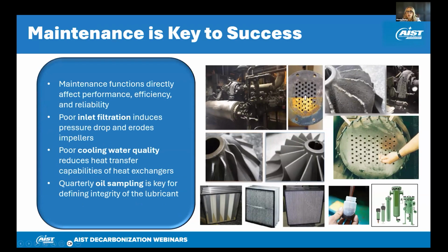I would highly suggest using the OEM branded filters for each particular compressor. They are designed with the purpose to protect the compressor. So these filters are designed with two stages. Typically, they're designed with a specific media and a specific micron filtration level, and they're designed with a certain number of pleats per inch. So that protects the compressor.